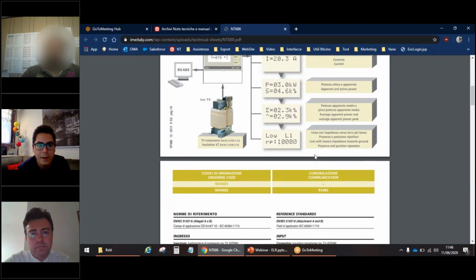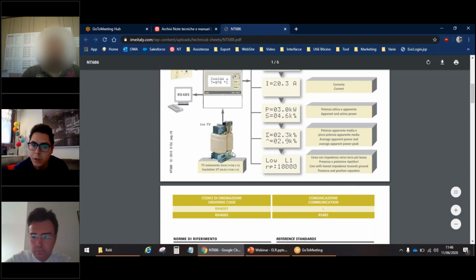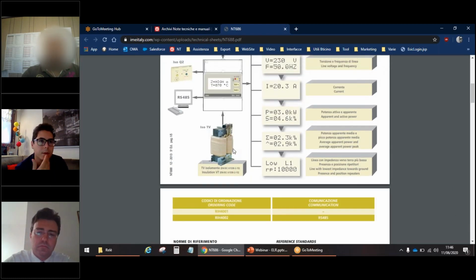So this is this one. As you can see, you have to connect this isolation relay to the isolation transformer. It's very useful in cases where, for example, in a hospital you have a surgical room, an operating room. You need to have the isolation of the surgery room from the external part of the hospital, because if you have a loss of isolation on the masses, you can cause electrocution of the patients. So it's very important that your surgery room is isolated from the rest of the hospital. So you have to use this instrument.